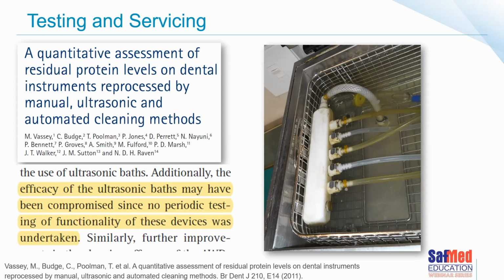The image on the right is one that I nearly cried at that particular day doing an audit in a particular CSSD. The contaminant over there is fungi. I mean, really, do we really want fungus growing in our ultrasonic cleaner? So that's a bath that's been left with the water in it for an extended period of time. Really, it's very sad to see this. For me, it's incredibly sad if I see an ultrasonic cleaner that's just not used properly or not even looked after properly. A very sad state of affairs.